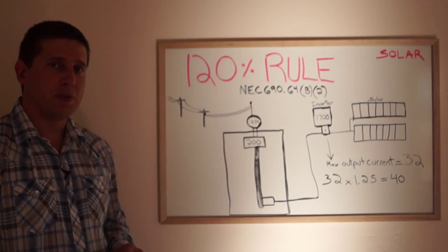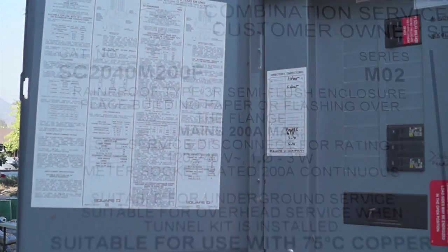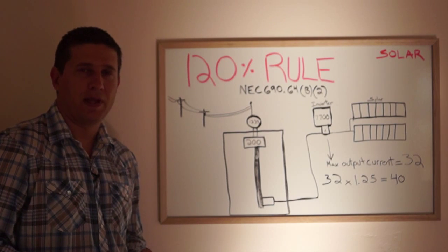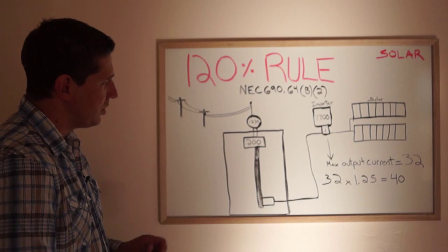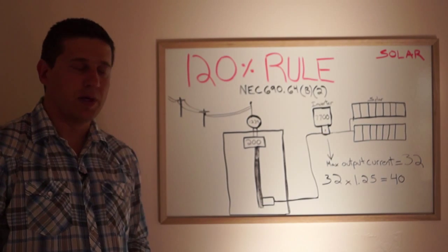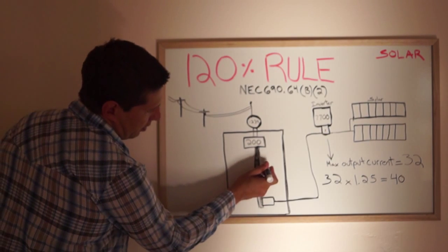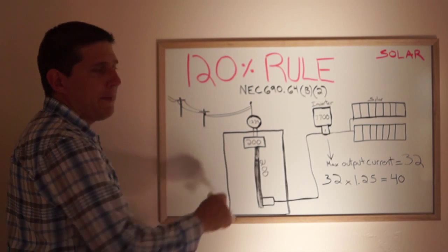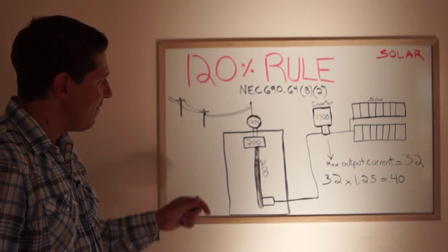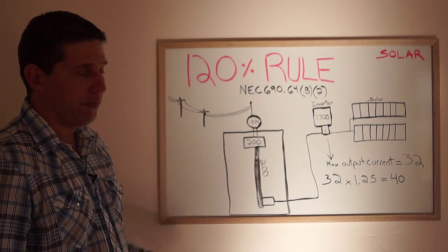Usually the label will state the bus bar rating which I encourage anyone looking into further understanding this to look at a couple electric panels and find the bus bar rating. Now assuming that this bus bar rating is 200 as well, meaning that bus bar wasn't designed to have more than 200 amps feeding through it.